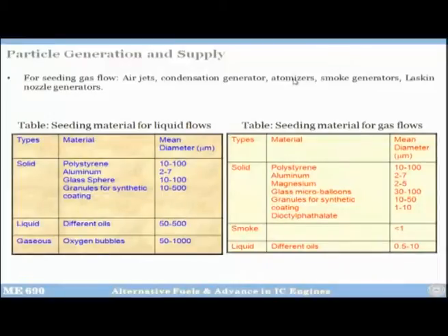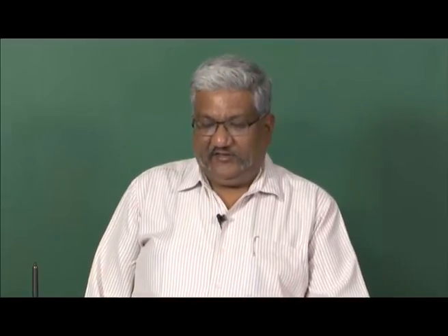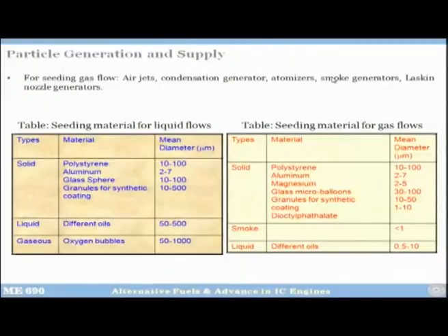There are atomizers. Atomizers are nothing but just like injectors. You have high pressure fluid passing through a small nozzle, it atomizes, and then the liquid in very small droplets is injected into the airstream. Then there are smoke generators.